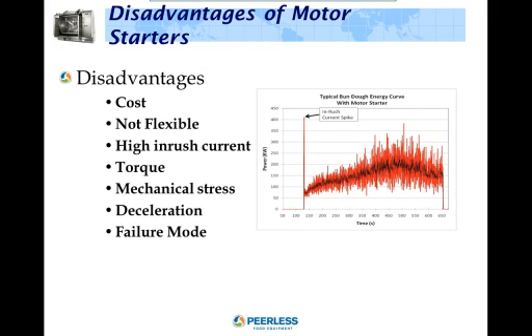Torque. Relatively low starting torque, 150 to 180% of full load torque, compared to the current draw. Almost all motor current here is reactive, and reactive current by nature does not produce torque. When a motor runs at speed, the slip is typically in the area of 1 to 3%. Under this condition, the reactive current is much less, and the motor produces rated torque at rated current. With a VFD, the motor runs virtually at speed during acceleration. Since the voltage is reduced at low speeds, the input current can be 10% or less with more than 150% torque.